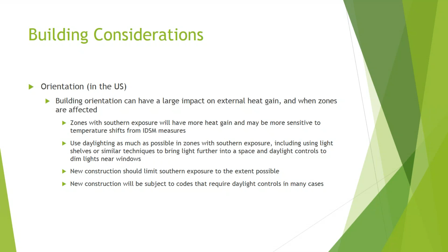New construction, particularly here in Southern Nevada where we've just adopted the 2018 IECC, has a requirement for daylight controls that is now fairly specific, requiring daylight controls separately zoned as you look at different orientations of the building. So another advantage of orienting a building at 45 degrees to a cardinal orientation is that you would only have 2 daylight zones, southeast and southwest, instead of 3 - east, south, and west - as you're looking at your control system. So considering how the building is going to be oriented is very important when you're looking at demand side management.